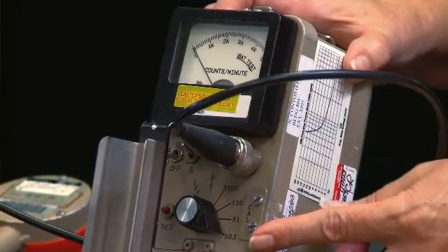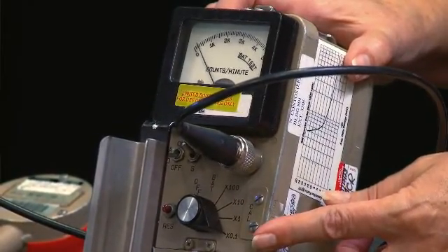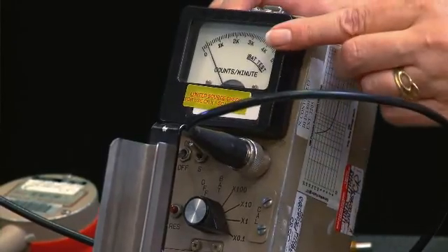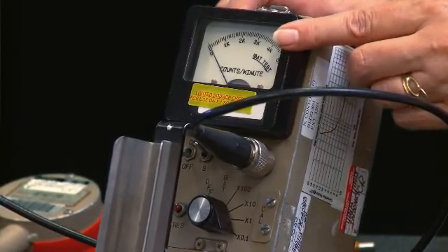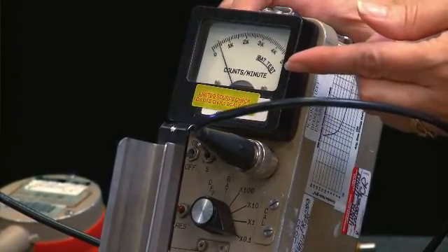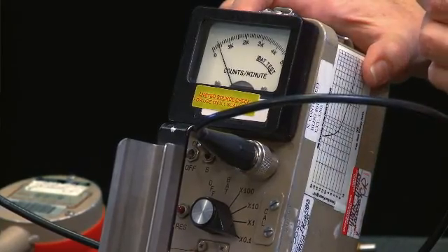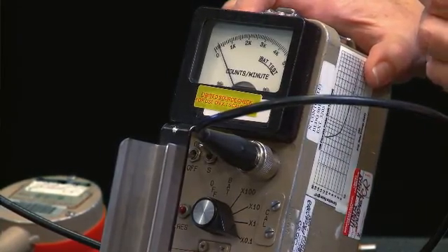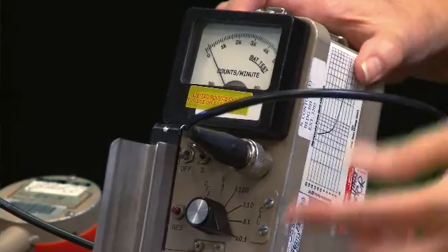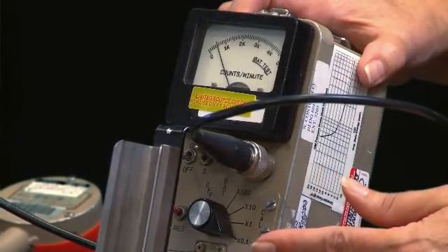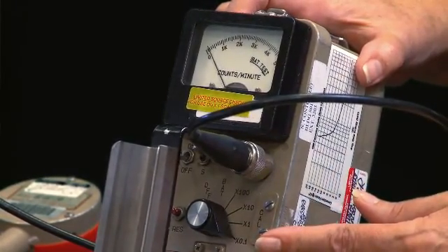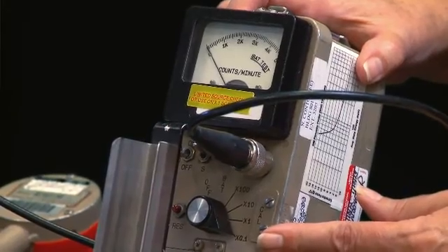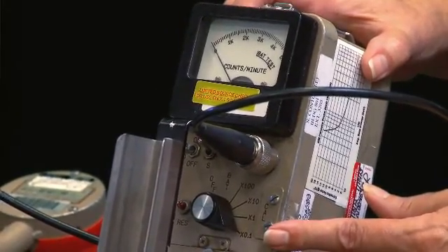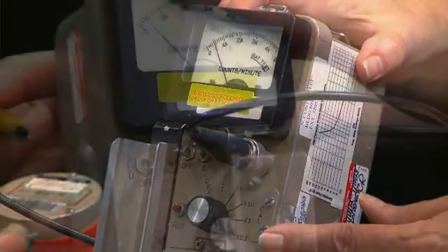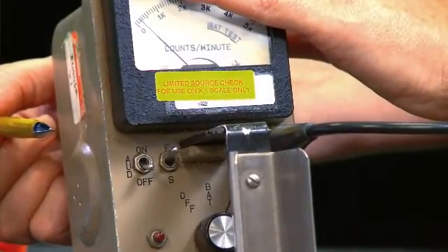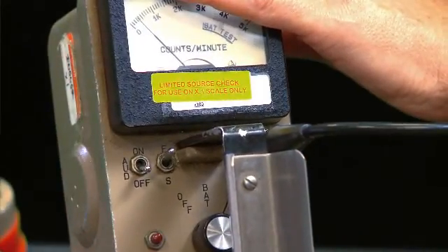you will need to select the range on the dial where you can best see the position of the needle. If the needle registers far to the left or far to the right, choose another range and note the counts per minute. It is very important that you record not only the counts per minute, but also the range where the switch is set. Failure to accurately record the counts per minute could lead to inaccurate action for a potentially contaminated individual. Note that there are 2 toggles, 1 button, and 1 switch on the meter.